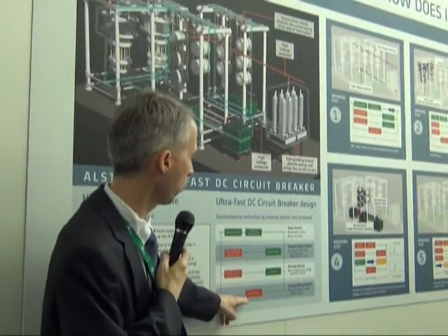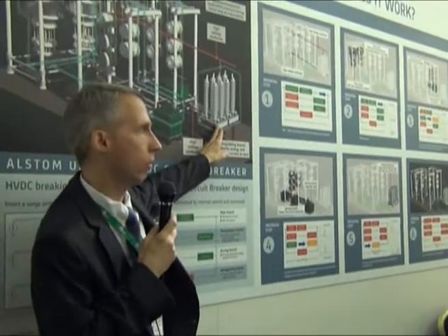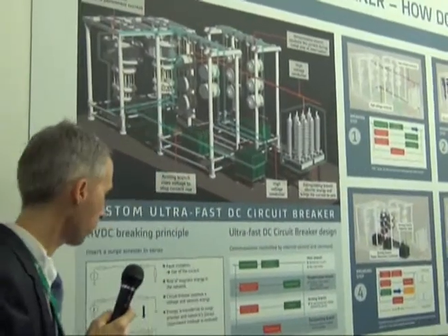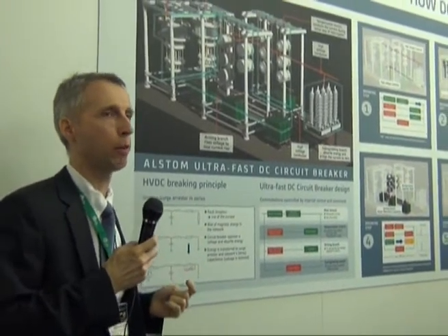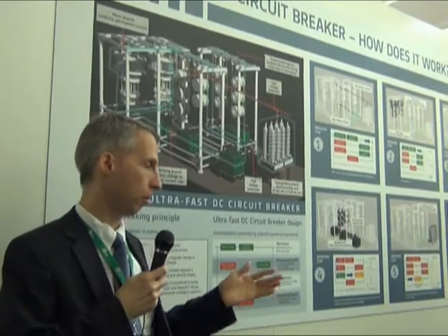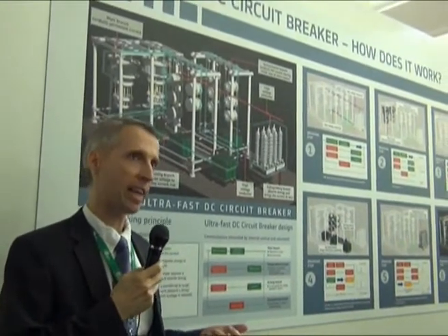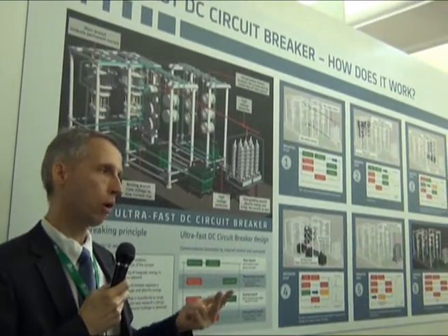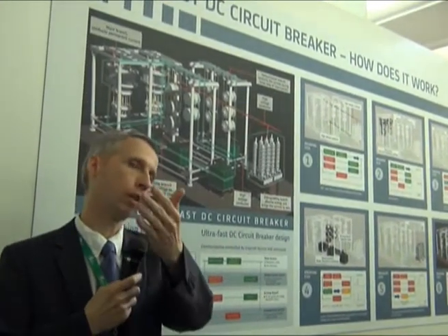Last but not least, energy absorption in the extinguishing branch. These over here are commercially available surge arrestors, nothing new. This is a first design made from scratch during a European funded project based on Alstom technology. However, within 3 years from the design that was numerically simulated, we had to make it, and without any standard, without any test procedure, without any test circuit, we also had to make the whole thing happen, make it real and test it, and the results are just behind you.